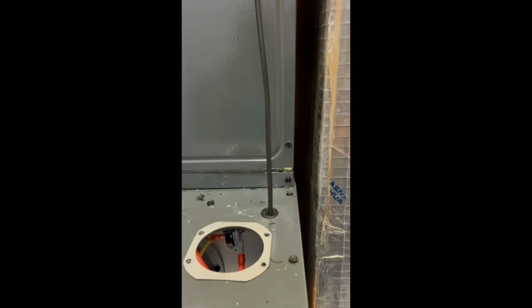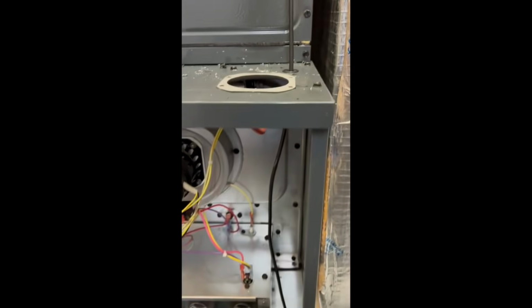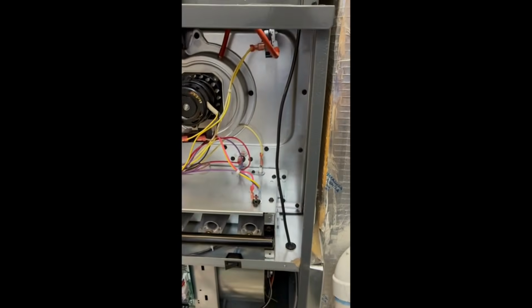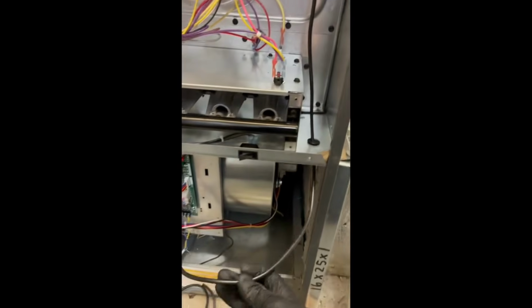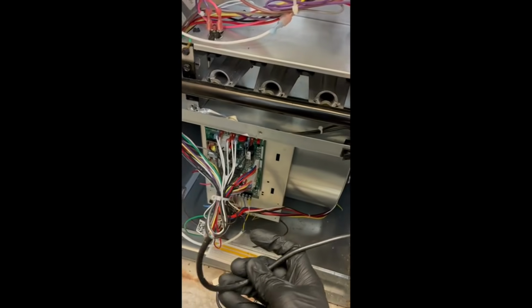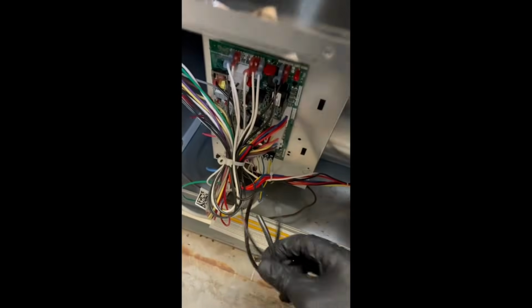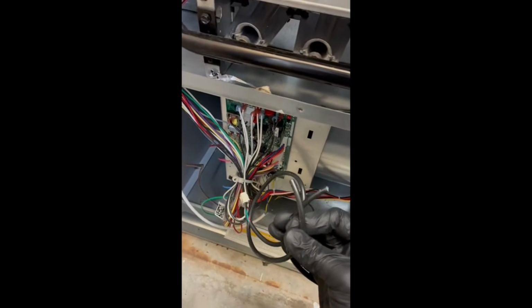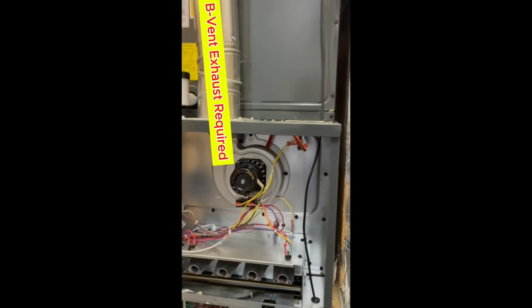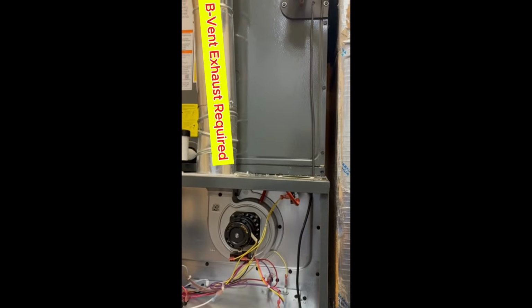I went through that rubber seal there and then did a plastic anti-short bushing down through the cabinet. I didn't know any other way to route the cable, to be honest with you. I didn't feel comfortable routing it down through where the heat exchanger goes. And I didn't see anywhere where the manufacturer gives you a clear path to run the cable. Unless I missed it, I couldn't find anything in the installation instructions either. But that's how I had to run the cable.